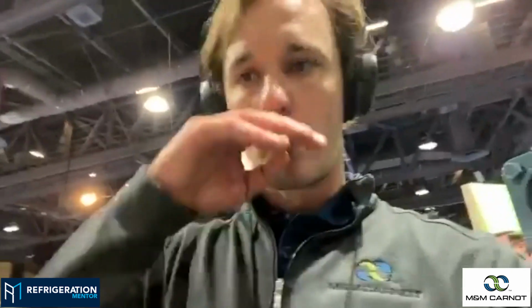Yeah, we have multiple designs. For supermarket, we've used a lot of the time the low temp discharge. Yep. And what's specific to M&M Carnot or industrial design, we use what we call the intercooler. Okay. So basically we're cooling down liquid even lower than you would normally have straight in your receiver to increase the efficiency of the low temperature compressors.